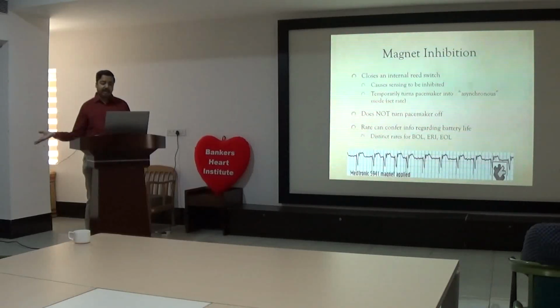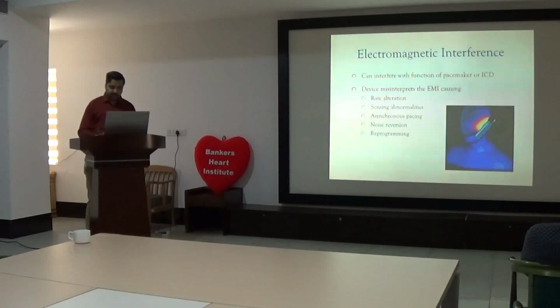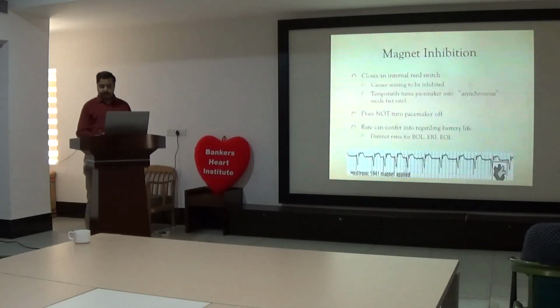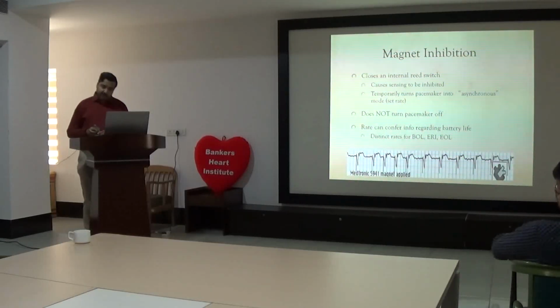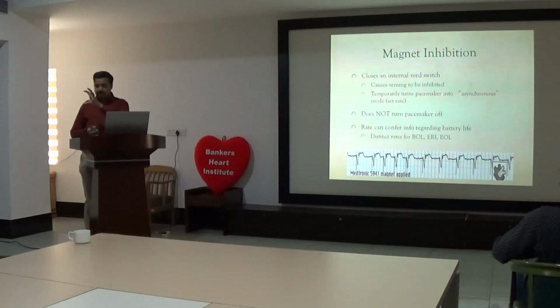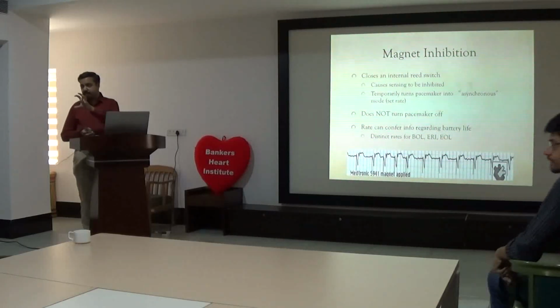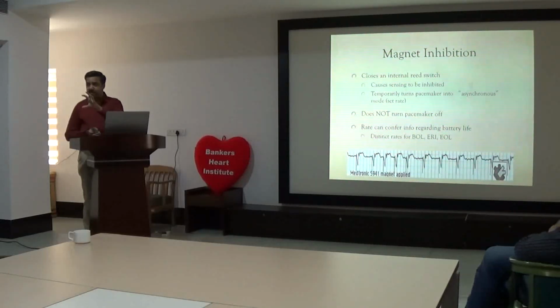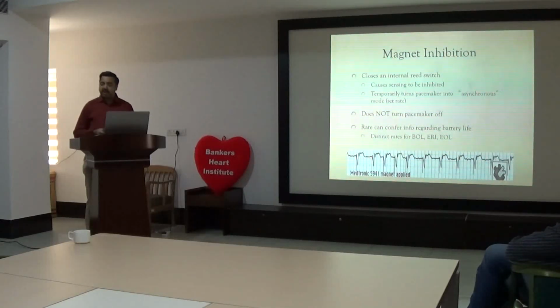So where do you apply the magnet? On the pacemaker, not on the patient. Yes, on the pacemaker. Can you apply it on the pulse generator? Yes, we can, but the magnet has to be this much in size. It won't be a small one. So in case of an emergency, if you want to go for surgery and the company representative is not available, you can use the magnet during surgery. That is the same as VOO.